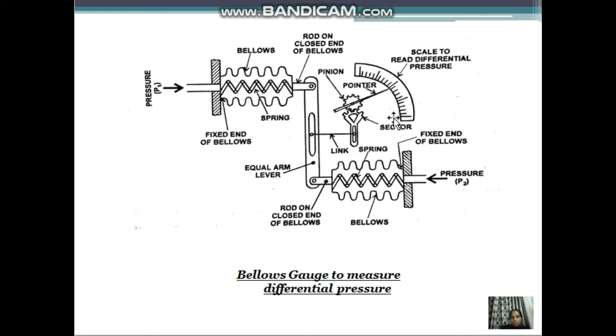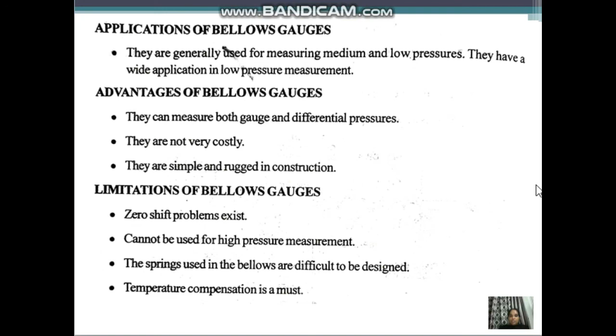Coming to the applications, we have already seen. Mainly it is used to measure medium and low pressures, and they have a wide application in low pressure measurement also. Advantages: they can measure both gauge and differential pressures, as we have seen now, and they are not very costly and are simple and rugged in construction. Coming to the limitations of the bellows gauges, they cannot be used for high pressure measurement, and the springs we place inside the bellows are difficult to design, and you always have to compensate for temperature before using the bellows. And next, there will be zero shift problems in these bellows pressure gauges.